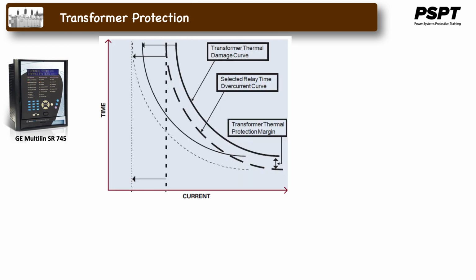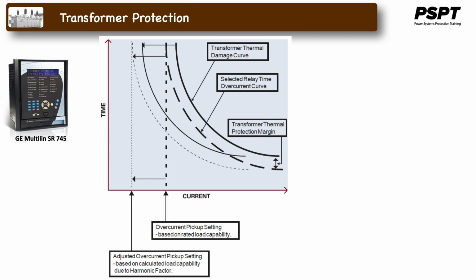The 745 can be used to provide backup protection for the transformer and adjacent power system equipment. Instantaneous overcurrent elements can be used to fast clear a severe internal fault or external through faults. Timed overcurrent protection elements per winding allow coordination with adjacent protected zones and act as backup protection. Timed overcurrent protection functions are provided for phase and ground currents.